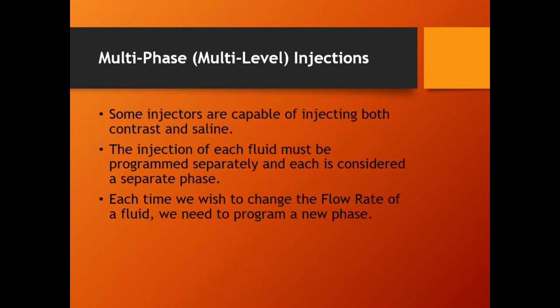Now remember, this is a 4-phase injection: contrast and saline, contrast and saline, and we hit start. Start the injection. First phase, second phase, third phase. Final phase. All right, that is a multi-level injection. Some of these injectors are typically a minimum of 4 phases. Some of them can go up to 8 phases. Most injections are multi-phase injections for CT and MRI. They don't necessarily do 4 or 8, but there's typically going to be 2 or 3 phases on most of your injections.